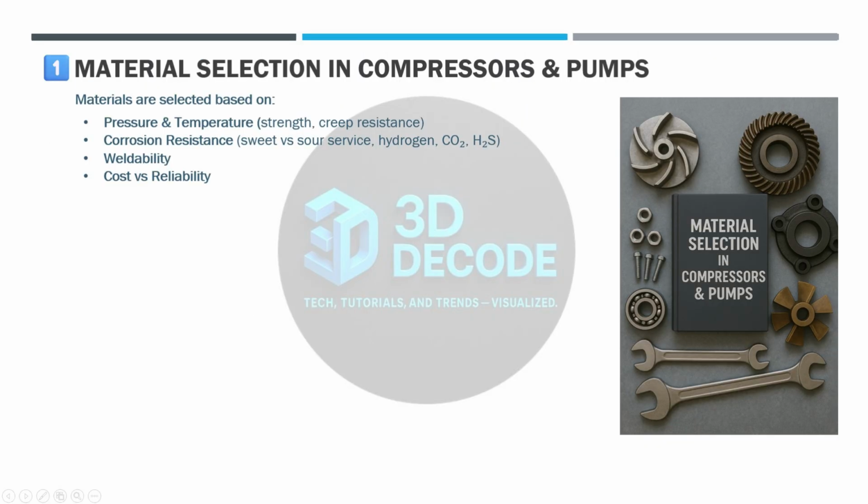When designing compressors, pumps, and packages, selecting the right material is just as important as the design itself. Materials are chosen based on pressure and temperature, strength and creep resistance, corrosion resistance, whether it's sweet or sour service, hydrogen, CO2, or H2S, weldability, cost versus reliability.